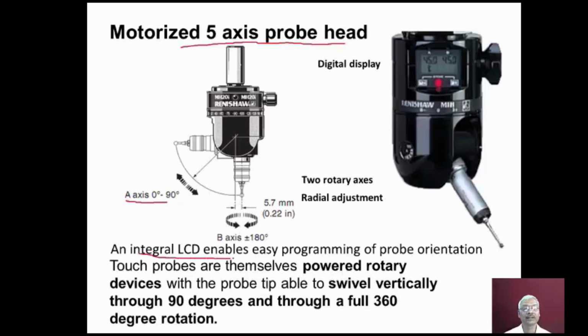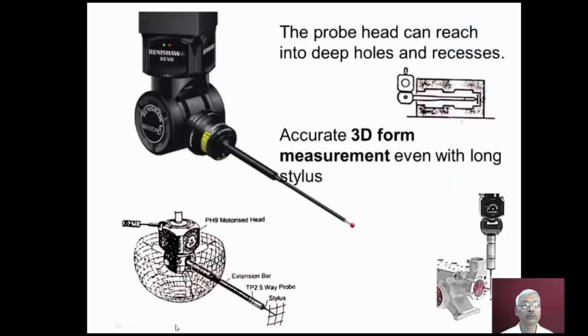There is an integral LCD display which enables easy programming of probe orientation. So depending upon the inspection requirement, the probe orientation can be adjusted. And this is the digital display built into the probe head. Now I can see here with the use of extended extension bars, probe head can reach deep holes and recesses, and the internal details, deep hole details can be measured. An accurate 3D form measurement even with long stylus is possible. You can see here by using the extension bars, the measurement volume can be selected.